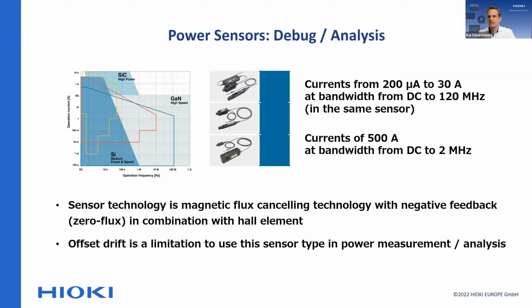So in case you say, wow, that's the solution for my power analysis - not really, because there's one downside: typically current measurements go on for a while, and these sensors are based on magnetic flux canceling technologies combined with a Hall element. The Hall element causes an offset drift, which causes inaccuracy in your measurement over a longer time. In theory you could degauss or demagnetize them, but you'd have to do that after a certain period of time, which is too short for power measurement or power analysis.